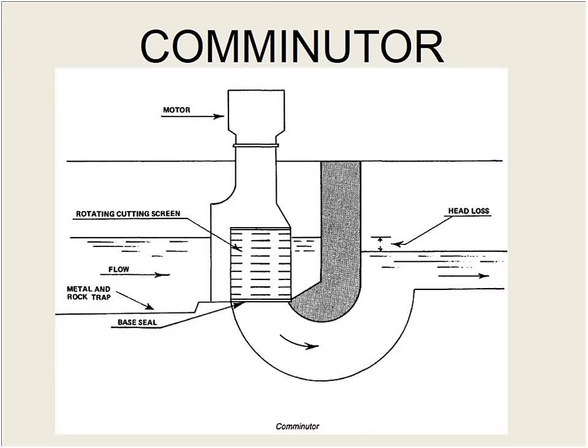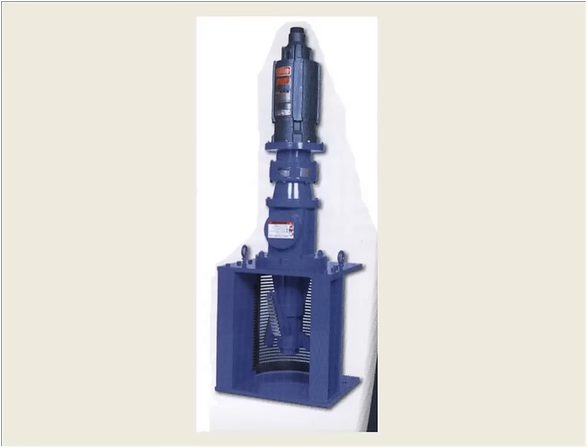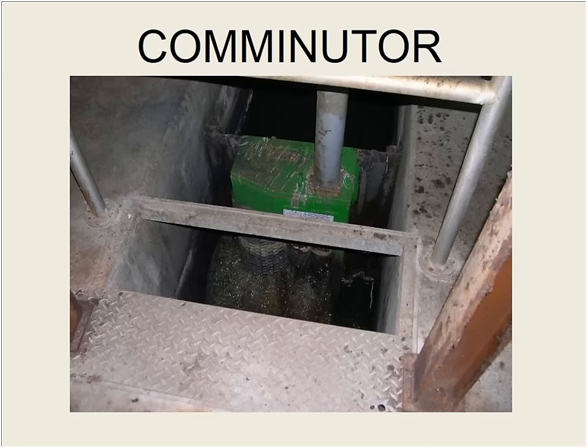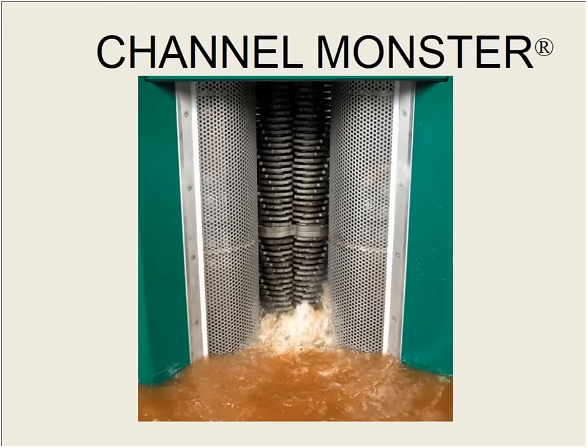Now, grinders are basically the same thing that you might have in your sink, a disposal unit, same kind of principle. The water's going to flow through here. There's a series of bars with certain spacing. Anything that passes through the bars is fine, but if it doesn't, it's going to get chewed up by the grinder. This thing just keeps going and chews it up until it passes on through. Just like that other unit we saw, you can throw pretty much anything in there and grind it up. So the difference between this and screening is screening actually removes this material and you can send it out to a landfill. This doesn't remove anything. It just chews it up and you have to deal with it later on.